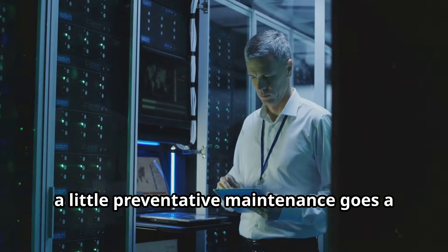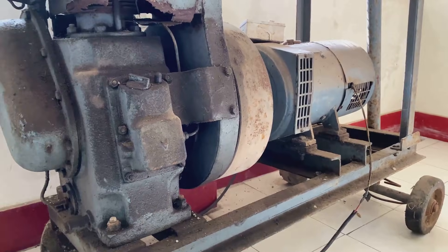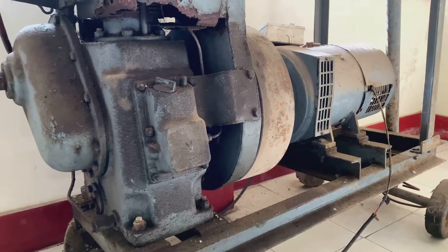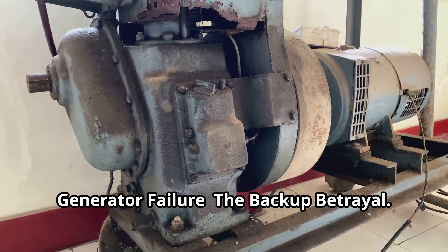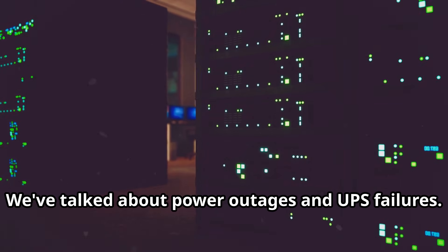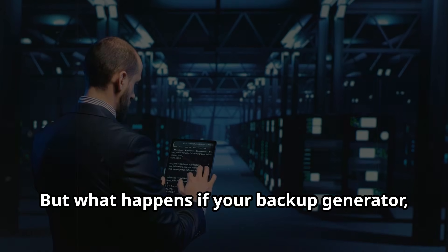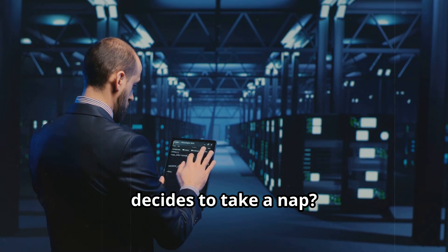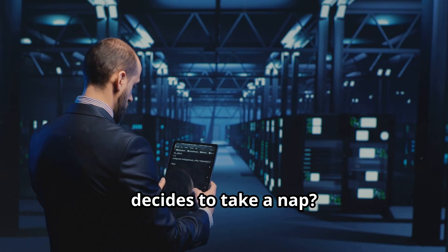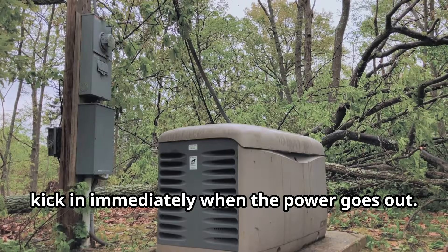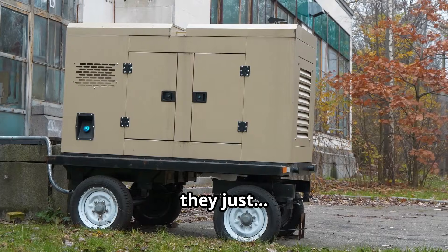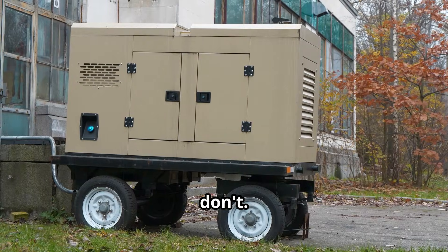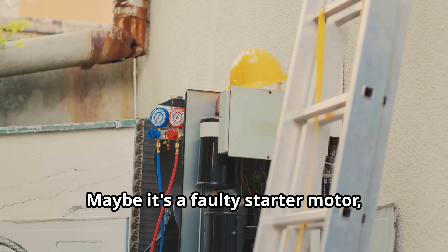Generator failure: the backup betrayal. We've talked about power outages and UPS failures, but what happens if your backup generator, the last line of defense, decides to take a nap? Those backup generators are supposed to kick in immediately when the power goes out, but sometimes they just don't. Maybe it's a faulty starter motor, maybe the fuel line is clogged.